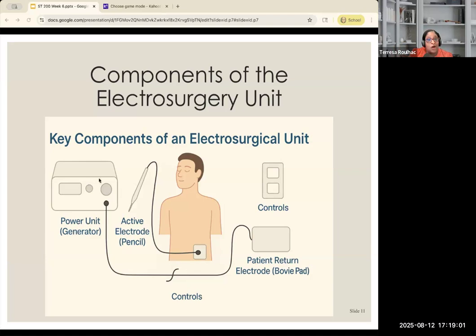The settings are on the machine. The controls are on the machine. The surgeon's preference card, which is the holy grail for us as STs, is going to let us know the preference of that machine for the instrument that's going to be connected to it. It could be that they want maybe a 50-50 mix, meaning 50 cut, 50 coagulate. They may say 60-40, and it's just going to depend on the surgeon's preference and pretty much where they were trained and what they're comfortable with.